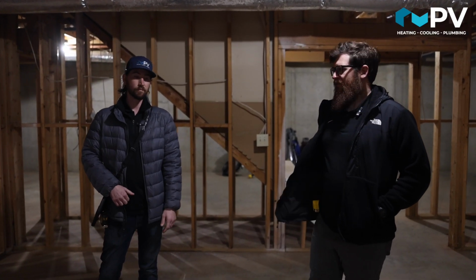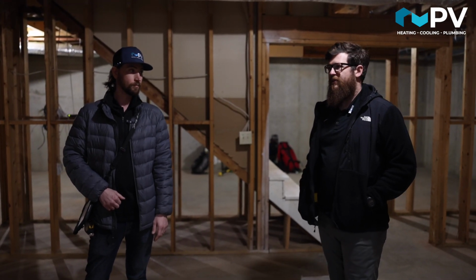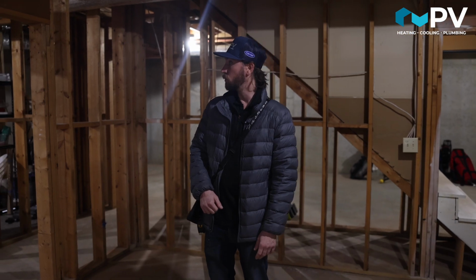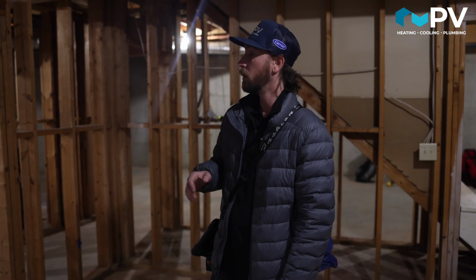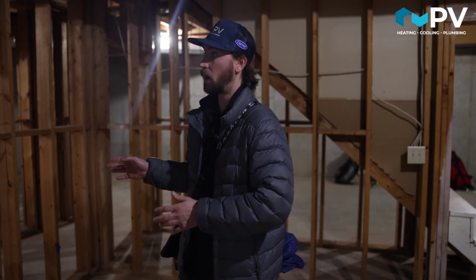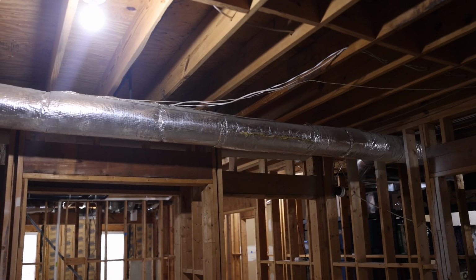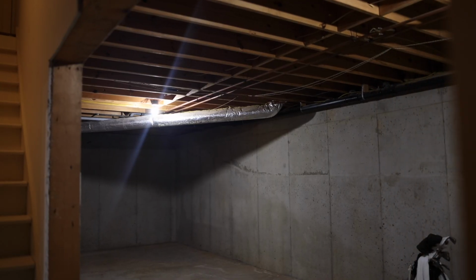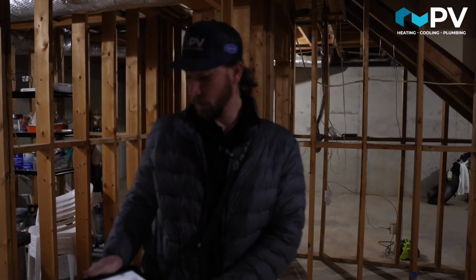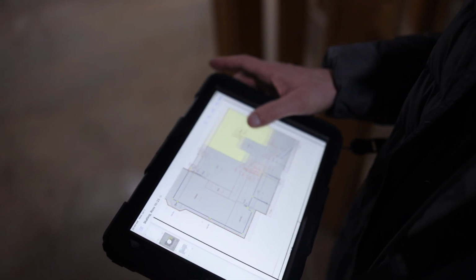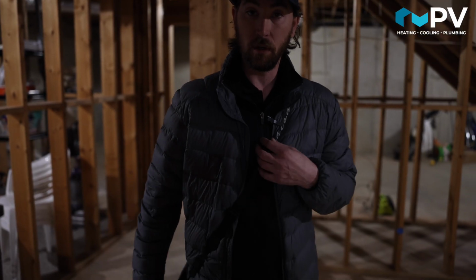Now we're down here in the basement with Matt from our design team. He's going to be going over some of the changes we're making to the ductwork to meet the client's needs. We're going to be converting to zoning, so we'll have two separate trunk lines, and the idea is to keep the ceilings as high as possible. We're going to be taking out a lot of the existing ductwork and wrapping around so we can weave our ducts in between the floor joists to accommodate what our client is working with. We use a manual J and manual D duct design to figure out which size ducts are proper for what the individual spaces need. We'll also be utilizing manual dampers after the install to make sure all the airflows are balanced properly for maximizing efficiency, performance, and comfort.